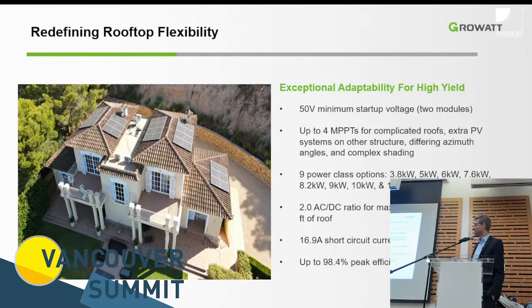The system is also rated for an extremely high DC to AC oversizing ratio, goes all the way up to 200%. And the reason for that is since you have a DC coupled system, you can, for example, as a 10 kilowatt for easy math, output 10 kilowatt continuous to the grid in a grid-tied application. And if you have excess power, that can be used at the same time to charge your batteries because everything is on the DC side, on the DC bus.